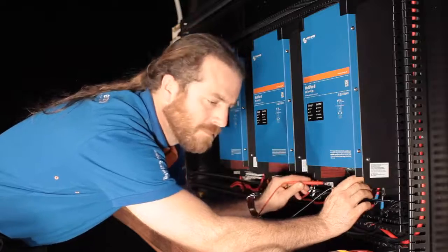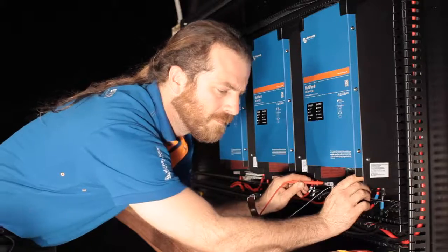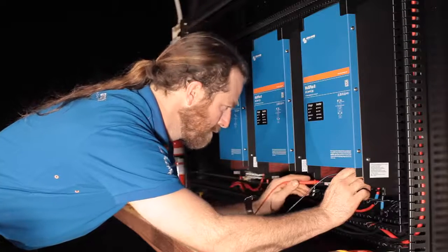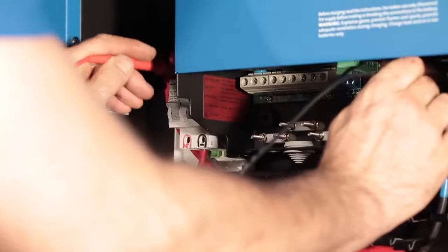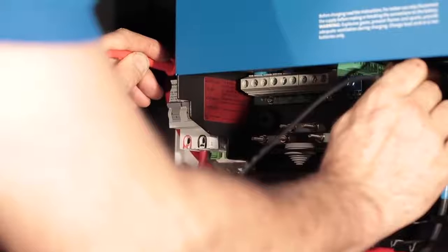Depending on the fuse you're using, there can be high inrush current on the Multi-Plus 2. So you may see a spark. In this case, the isolator is sealed up, so we won't see any connection point. But be mindful, doing this repeatedly can burn out the contacts on your isolator, so make sure it's appropriately rated for DC current.